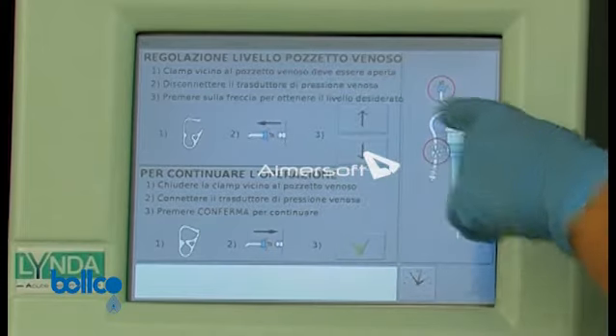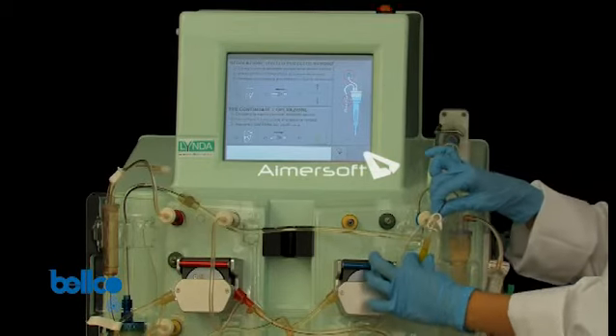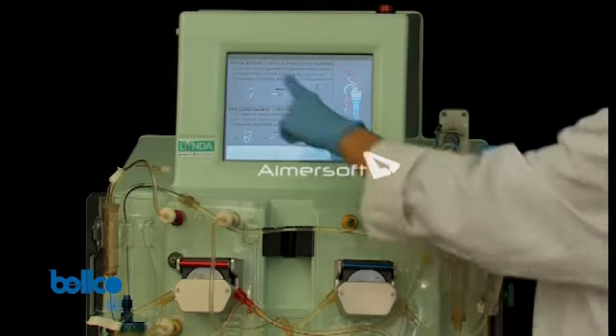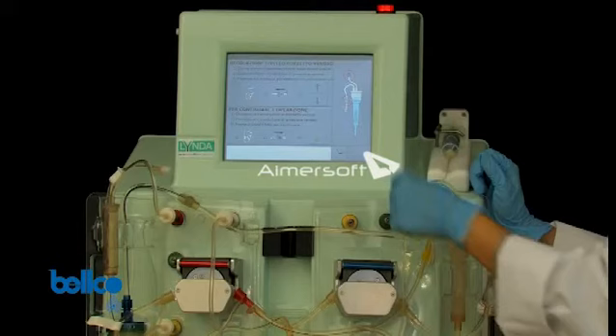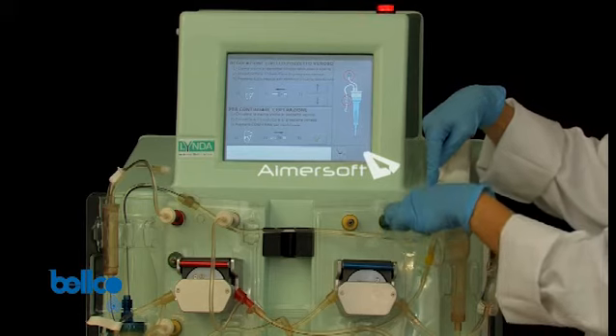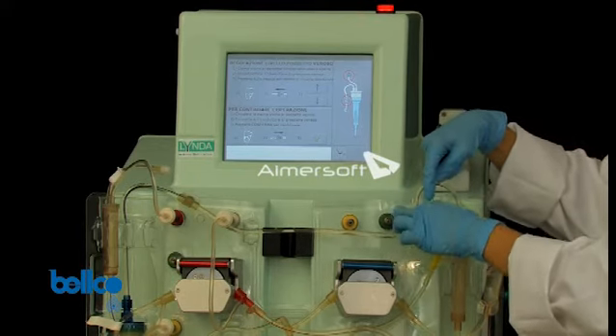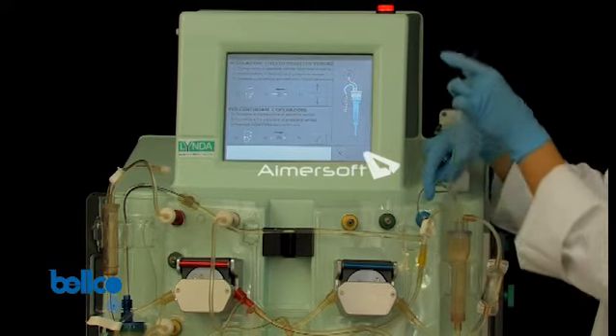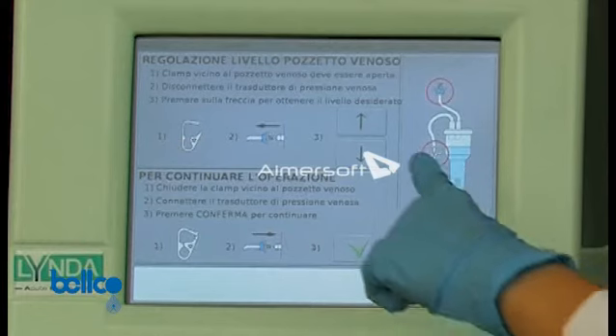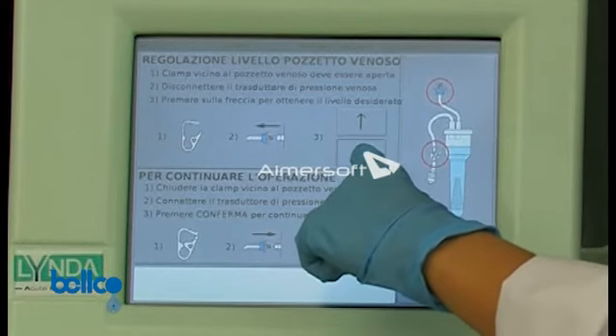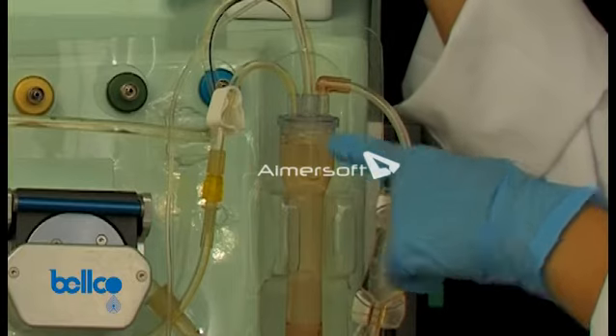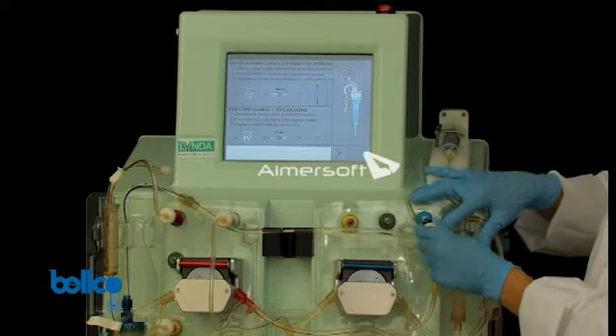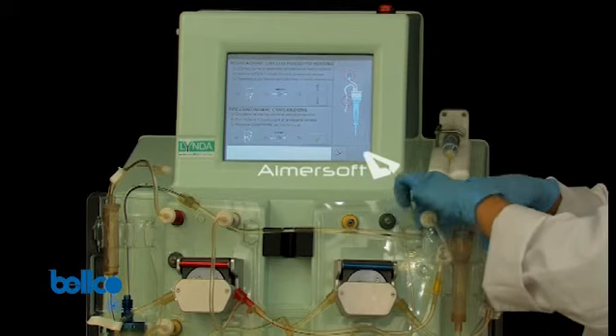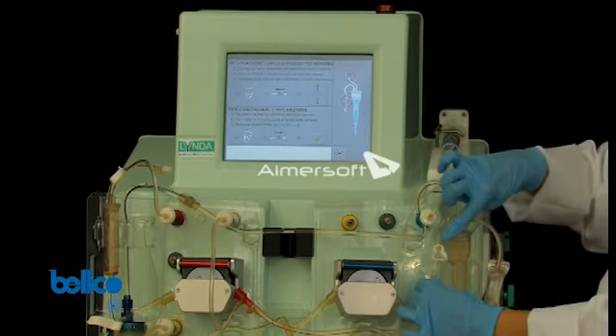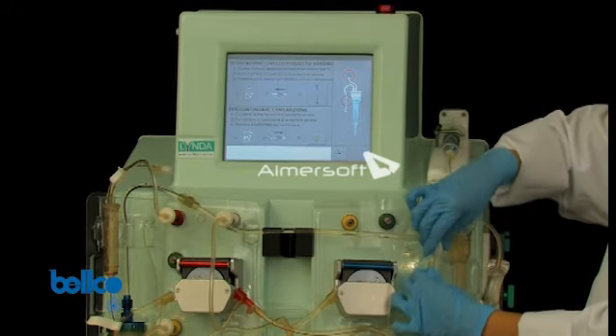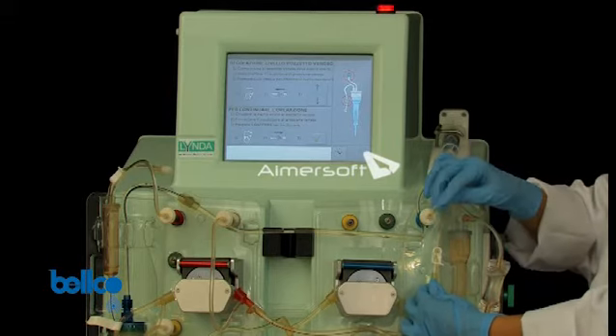At the end of priming, you need to adjust the venous chamber. The clamp near the venous drip chamber must be open as shown. Disconnect the venous pressure transducer and adjust the level in the drip chamber using the arrows on the screen. When done, reconnect the venous pressure transducer to the machine and close the clamp near the drip chamber. This clamp must stay closed throughout the treatment.